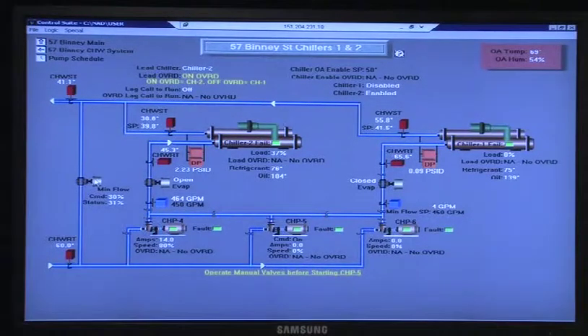Right here. This bypass valve is opening and closing based on that flow rate. They need to get that pump to flow that much. If it's higher than that, you can bypass. If it's lower than that, you've got to flow through that chiller. So that's what that is all about.